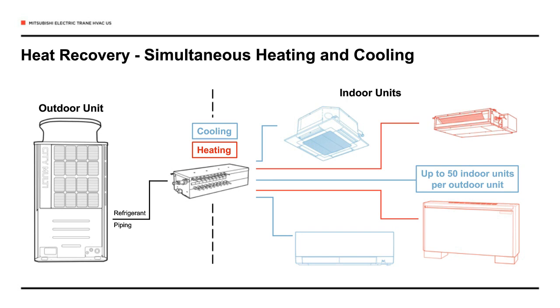So here again, you can see the outdoor unit on the left connected to refrigerant piping with the BC controller, which is that box just to the left of center, connected again to a variety of indoor units. But you can also see with the depiction of the blue and red lines that some areas are in heating mode while some areas of the building are utilizing cooling. So in the other example, instead of all indoor units being in one mode, a heat recovery system is capable of simultaneous heating and cooling.